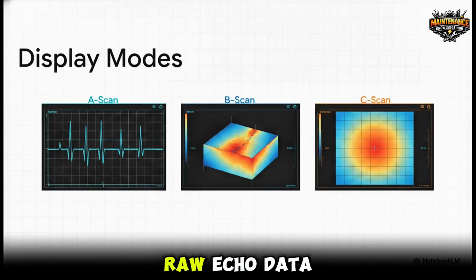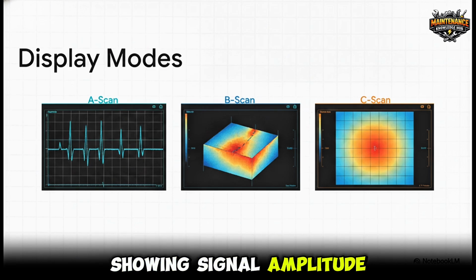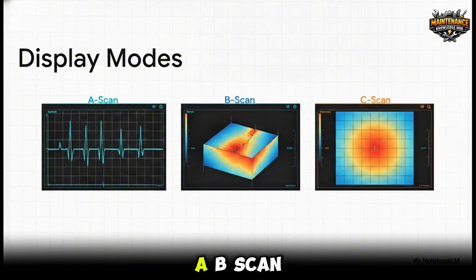Now, all this raw echo data has to be read by a human operator. The flaw detector visualizes this in 3 distinct display modes. The A scan is your bread and butter, definitely the most common. It's a standard 2D graph showing signal amplitude on one side and echo position on the other. A B scan steps it up a notch by providing a really neat cross-sectional view of the material. And finally, a C scan gives a plan or top-down view.